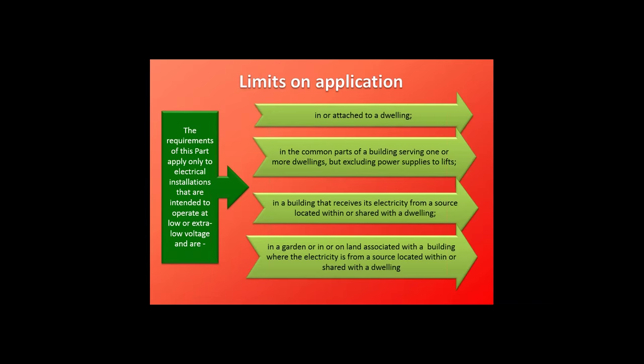We have to look at the scope of the building regulations and what they apply to, because they don't cover everything within the domestic dwelling — only particular risk situations. The requirements only apply to low or extra-low voltage installations. This is the sort of installation we come across within a domestic property, including something connected with that dwelling — it might be the installation in the dwelling itself, or something supplied from a supply in the dwelling that is outside the property, perhaps in an outbuilding or within the landscape attached to the property.